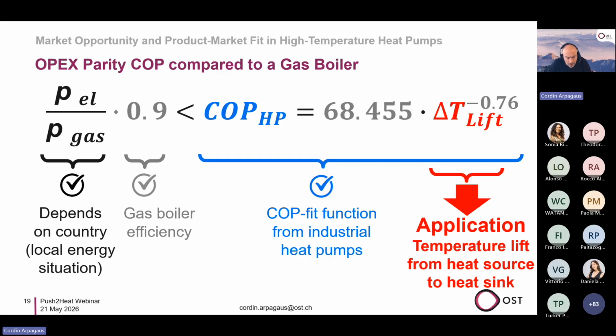And the gas boiler efficiency, 90%, let's say, is also somehow given. And the COP has to be higher than that. That's a very simple formula. And we have now this relation to the temperature lift to the application. So we know this fit formula from industrial heat pumps. We know it and can now link all that to this application. And so we have three factors: this price ratio, the COP, and the temperature lift.